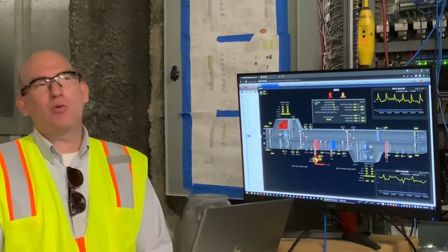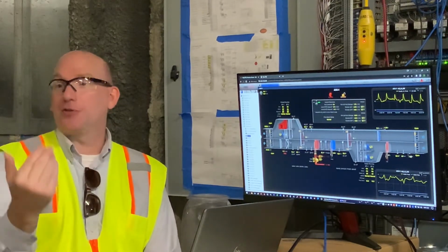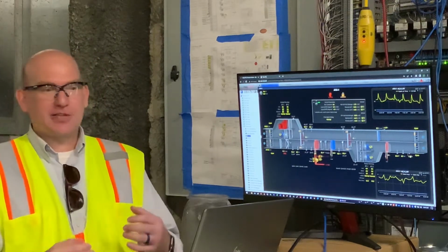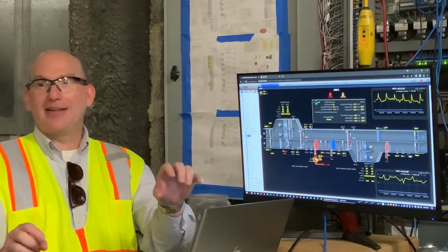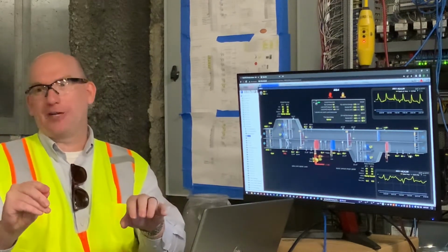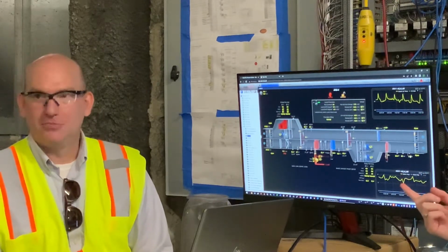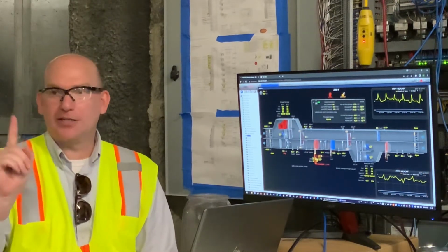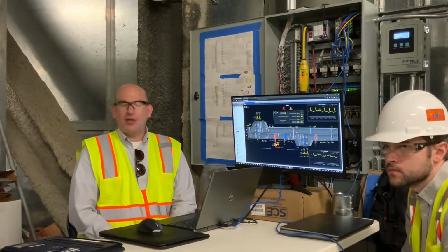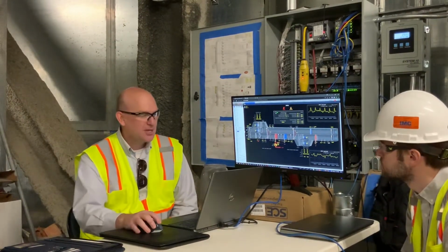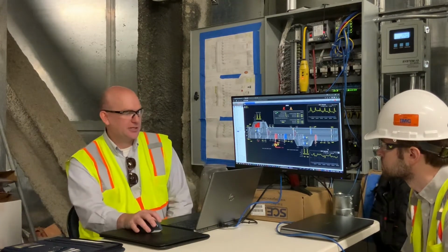Previously, we would actually pick up contacts right on the smoke detector and tell if it tripped. Nowadays, the fire alarm system has the smoke detector tied into it, and then there's a relay, and it makes a decision as to whether it closes that relay for us. If there's 4 or 5 different smoke detectors on the unit, we're just picking up one. We only get one signal, so we don't know if it's the return or the exhaust. The fire alarm system would tell you. So it's more and more common, especially in large buildings.